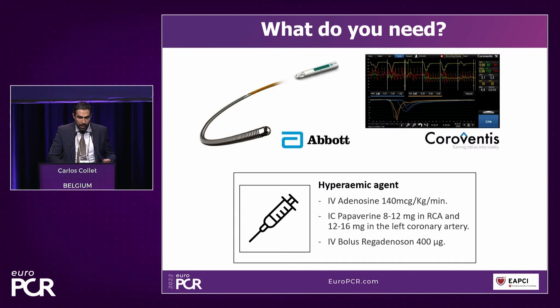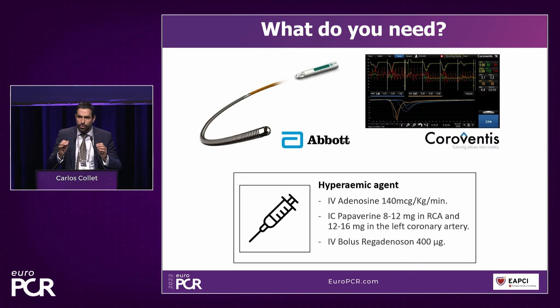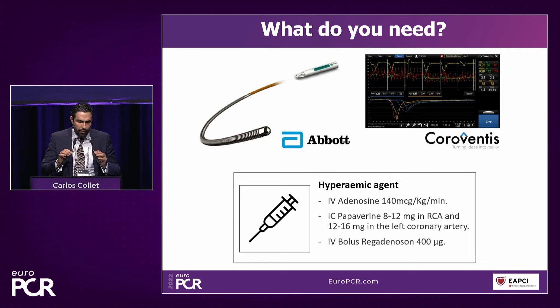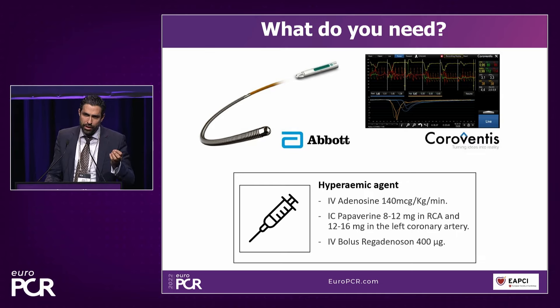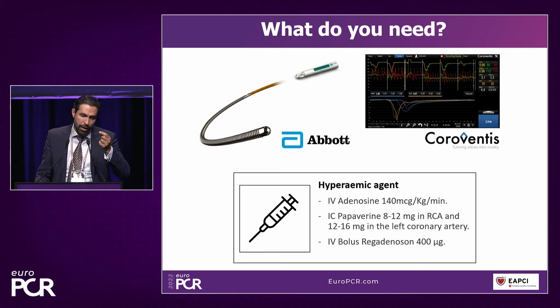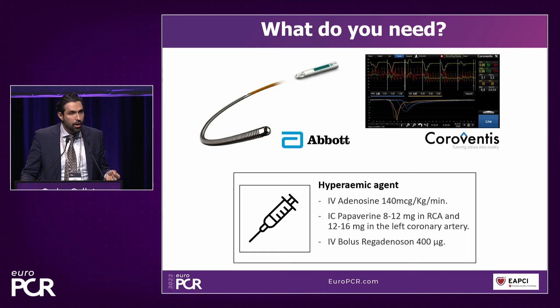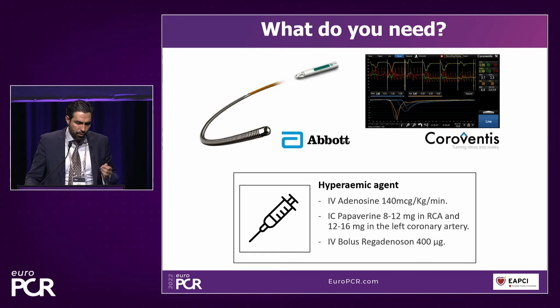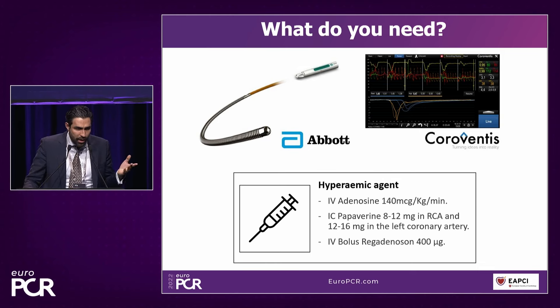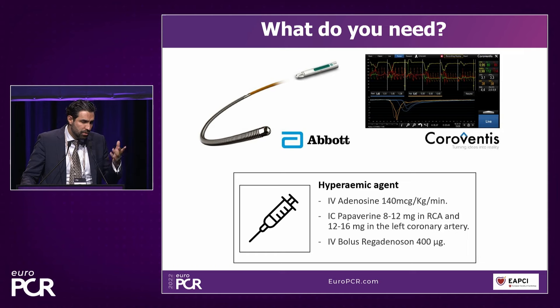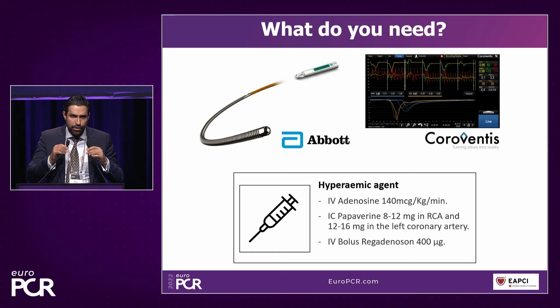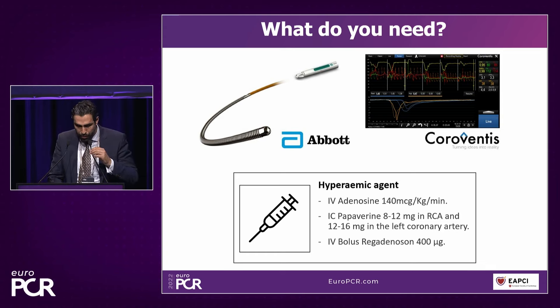The three things you need to start assessing the coronary microcirculation are: one, the PressureWire X from Abbott, which has in addition to the pressure sensor a temperature sensor at the tip; two, the CoroVentis console to sense changes in temperature; and three, a hyperemic agent. Classically IV adenosine has been used, and this is most common in some labs. The case will be done with IV adenosine, but we have now shifted to papaverine, which also makes things very simple. We're going to see a video of how easy these measurements are performed in the cath lab.